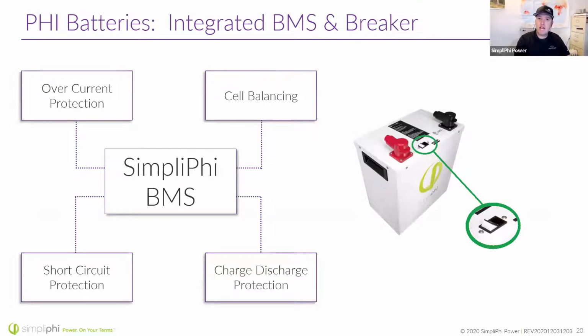All of our batteries have a built-in battery management system. We have 3 types. Our standard Phi battery has an analog, internal-only battery management system mainly there for cell balancing, but it also gives you overcurrent protection, short circuit protection, and charge and discharge protection. It's really there as the last line of defense to protect the battery, not an excuse for a poorly sized or poorly programmed system.